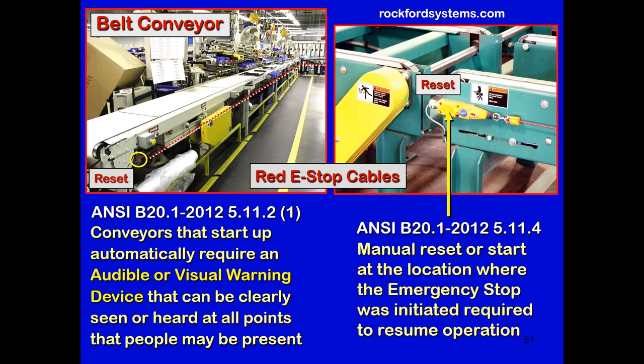With conveyors, you oftentimes can use a grab wire e-stop cable, also known as a rope pull e-stop, in lieu of putting a series of red emergency stops along the line of the conveyor, because that could be a lot of stop buttons. So the grab wire cables can go a long distance, and they can be strung around the corner, as you see in the top left there. Now, on the right-hand side, you can see where there's a manual reset for the grab wire system. And there's a yellow cover over rotating components, because remember, anything that rotates that could tangle up your hair or clothing is required to have a guard or cover up to a 7-foot level.